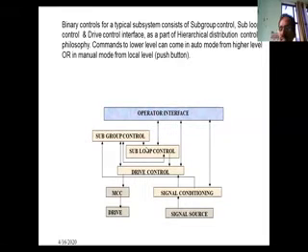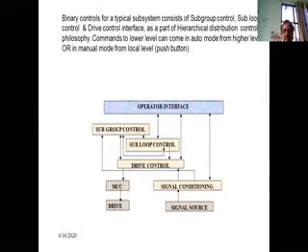Get it? Yes, sir. Same analogy is used in power plant also. It is in drive control, subloop control, SGC control, and these three parts are part of the secondary instrumentation of the DCS or PLC. Up to this we are in DCS and PLC. Then MCC and signals. MCC is in the electrical panel. Then drive is in the field. The signals or feedback signals may be at the drive as well as in the process, in the field.